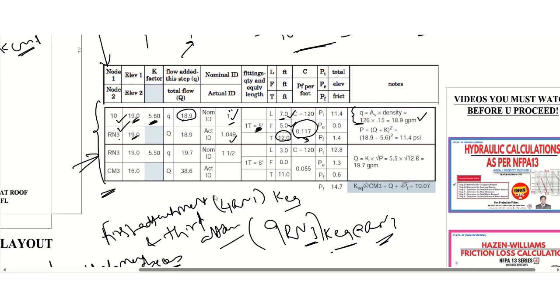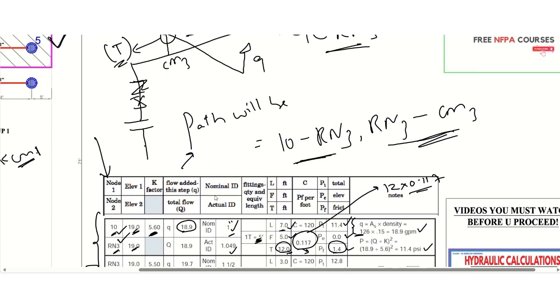And then the length between 10 and RN3 is seven feet, so total will be 12 feet. And here we calculated the friction loss by using Hazen-Williams friction loss formula, which was already explained earlier. And apart from that, we have calculated the total pressure 11.4 PSI that we have mentioned here. Elevation is zero since the elevation for 10 and RN3 both are same. And the friction loss will be 1.4. We have to multiply 12 by 0.117, so we are going to get about 1.4.